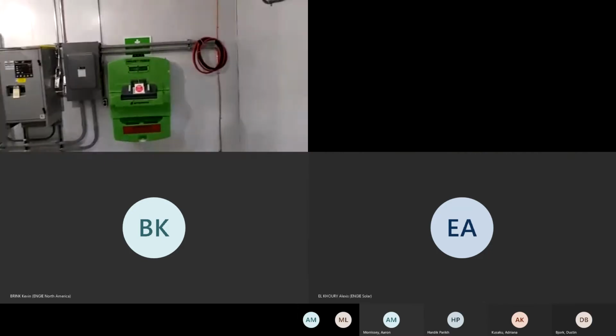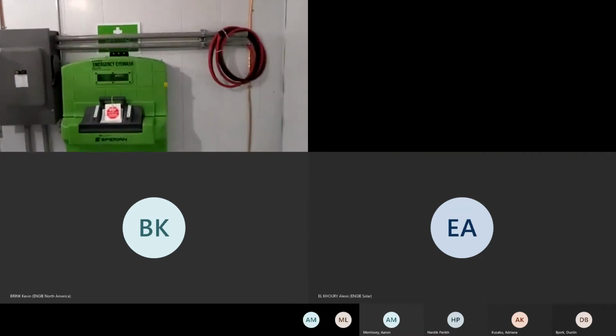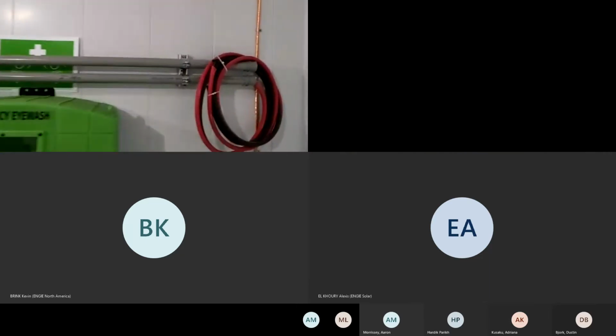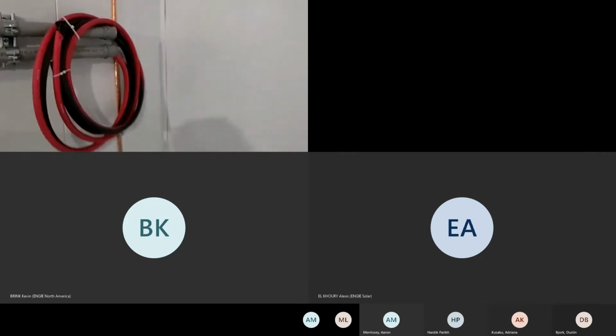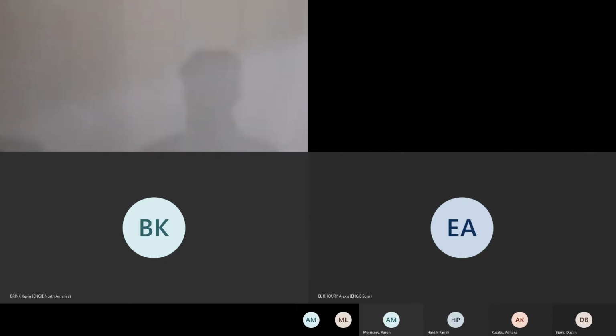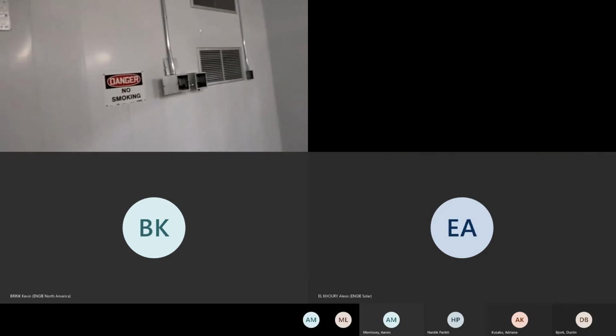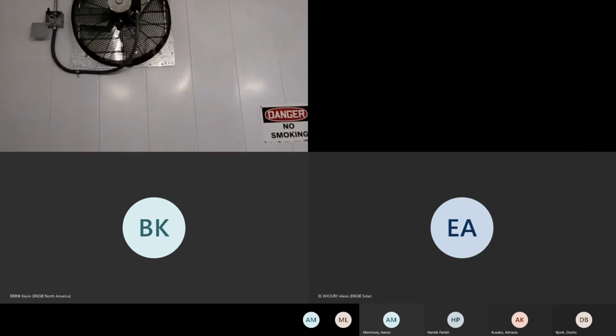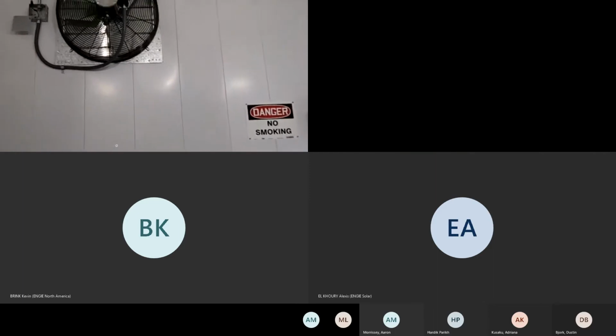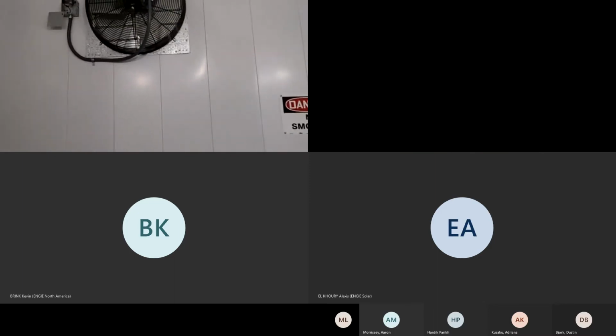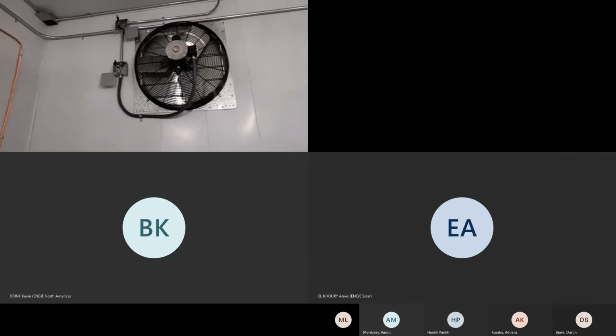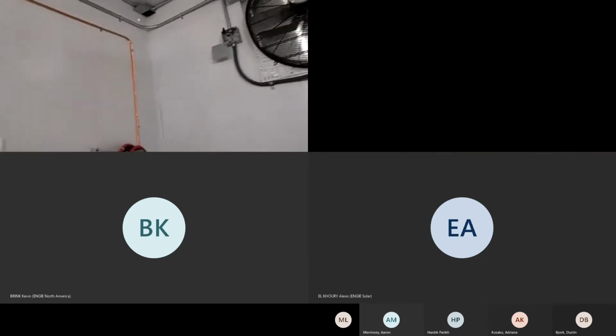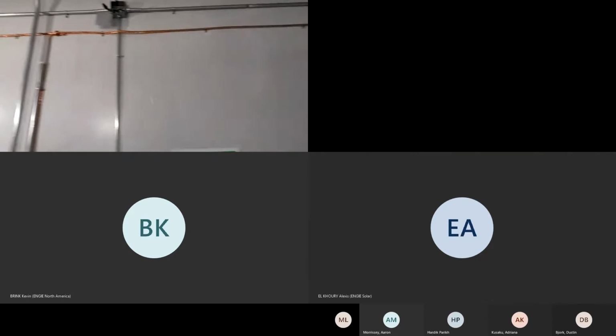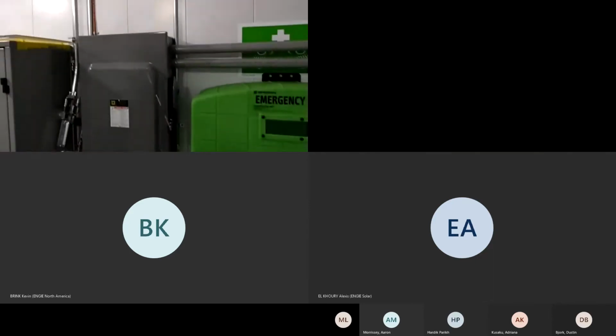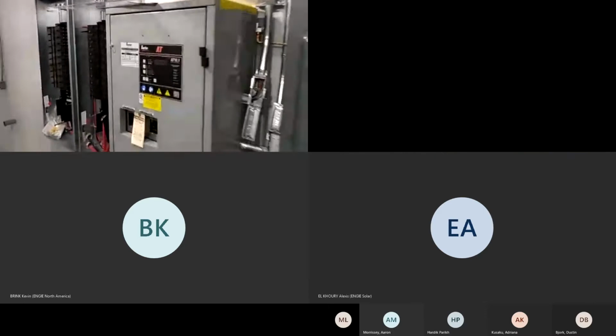So just to give you an idea of what the inside of a building is going to look like, similar to yours. On this area, we have the battery cables, the DC cabling, so that tells you the batteries are going to be installed right here, which makes sense. We have the HVAC there, and then the exhaust fan here. This is a pretty large exhaust fan for this size building, but it's what the customer asked for. Up here for house wiring, we typically do a raceway, but this customer has asked for conduit all around the exterior of the building. Then we have the auxiliary panels and the battery charger.